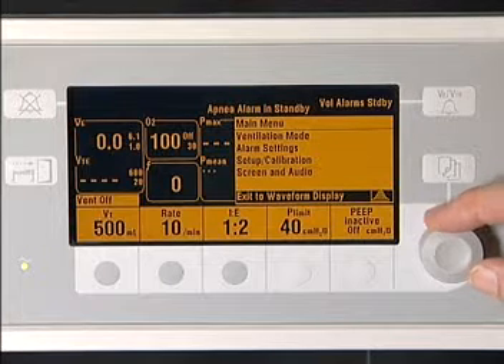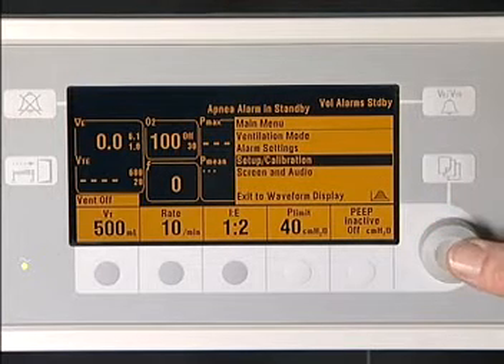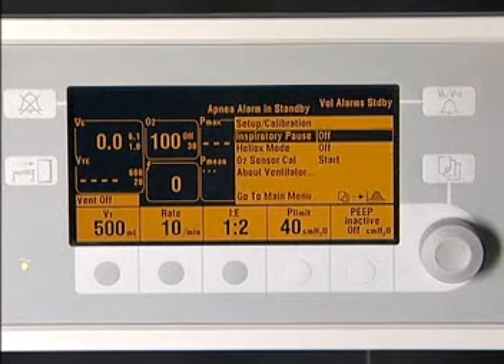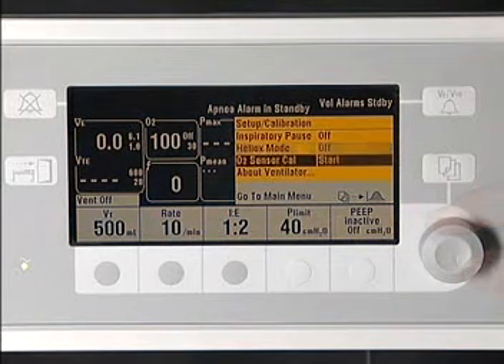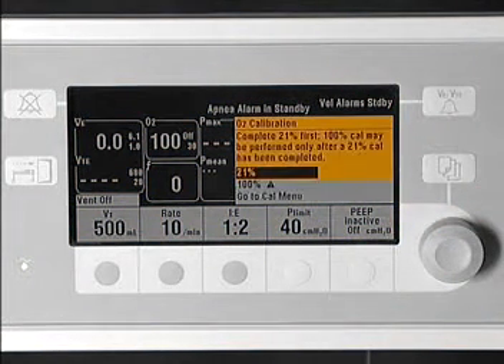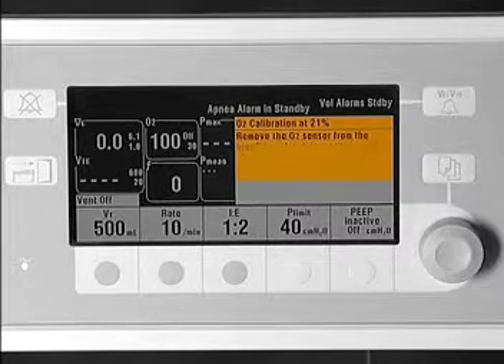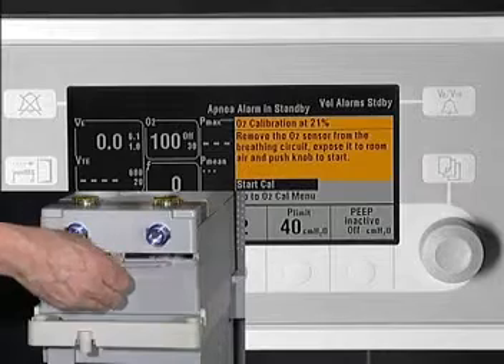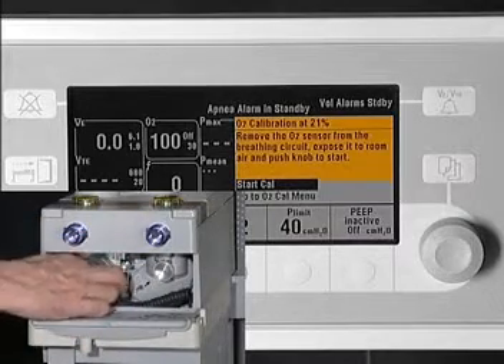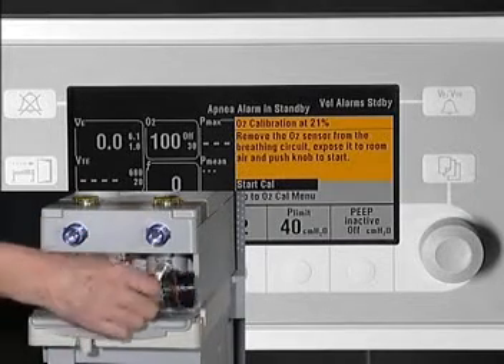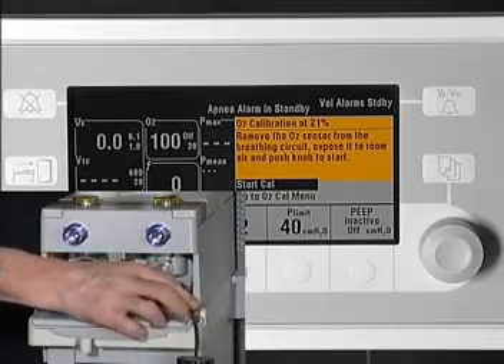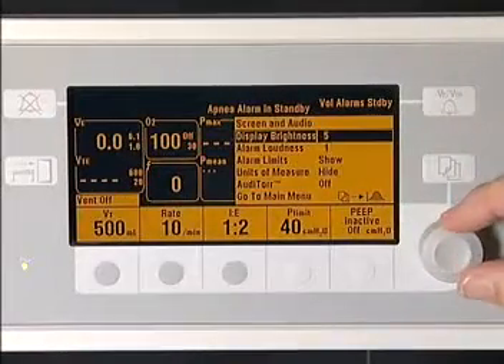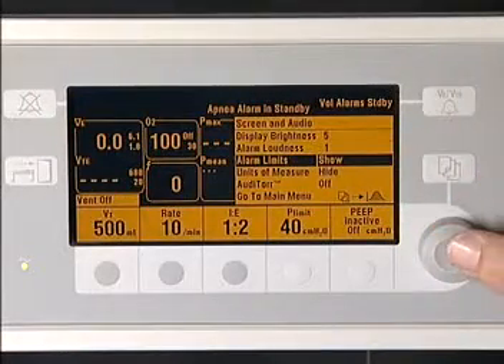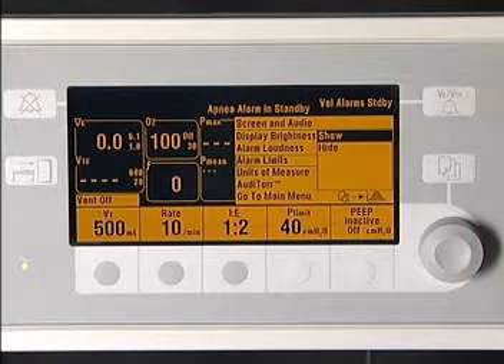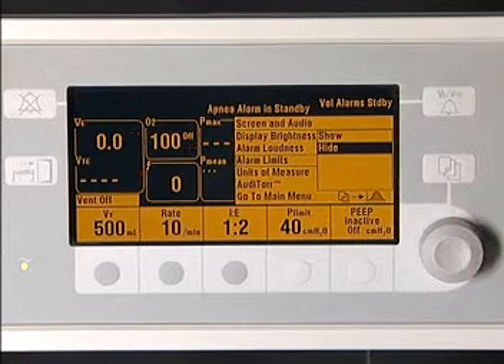A quick review of the menus indicates the submenus available to the operator: alarm settings, ventilator setup, screen and audio setup, and calibration. Choices which require operator involvement, such as calibration of the O2 sensor, step the operator through the necessary interventions on their part. A menu selection allows the operator to decide whether to hide or show the alarm limits adjacent to each monitored parameter.